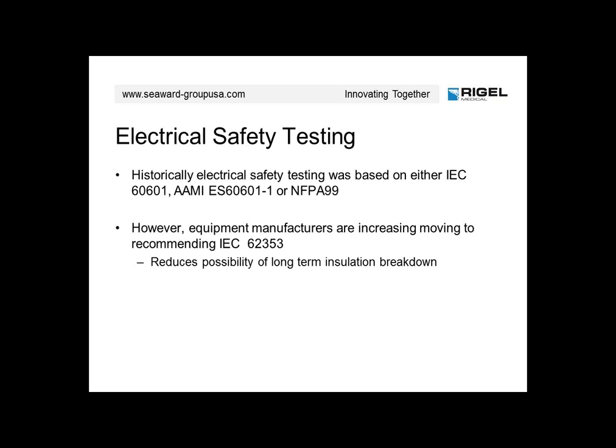So, electrical safety testing. Historically, safety testing has been based on a couple of standards: the IEC 60601, AAMI's version of that, the ES 60601-1, or the NFPA 99, which some states have adopted and mandated the use of that particular standard. And of course, they just came out with the latest version of that, NFPA 99-2015.